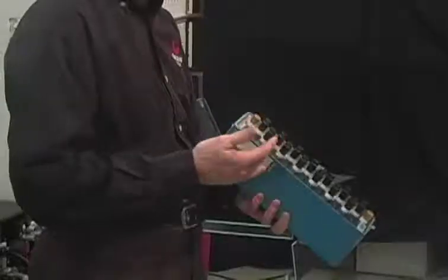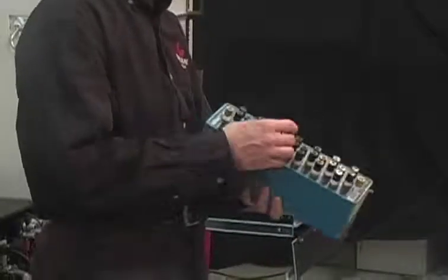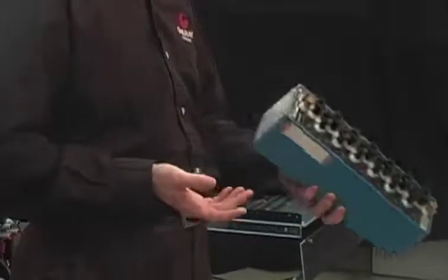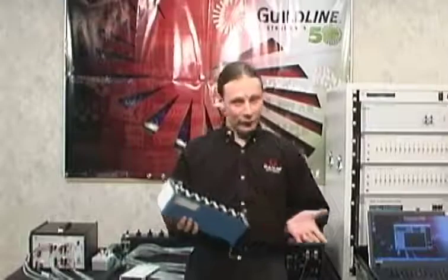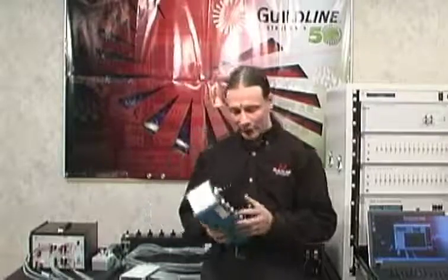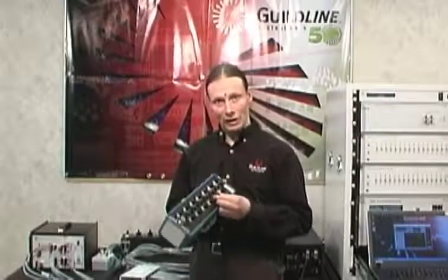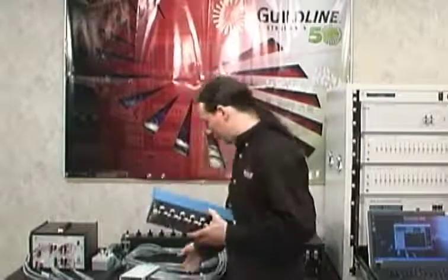And these things are essentially Hamon transfer standards that allow you to ladder up and ladder down, used to calibrate things like DMMs and that sort of thing. So we have a utility inside BridgeWorks that allows us to do the calibration of these things automated.